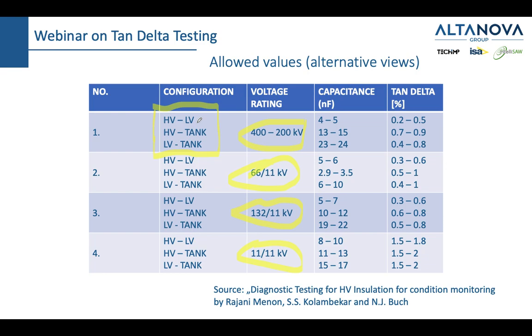what we can see is that for extra high voltage, the insulation between high and low voltage side should be very good, between 0.2 and 0.5, which is much less than 1%. High voltage versus tank is between 0.7 and 0.9. If it's smaller, even better. And low voltage tank is between 0.4 and 0.8. And also we have some capacitances here. Now, a capacitance is really difficult to assess. It's not difficult to assess, it's difficult to say what would be the nominal values because it depends heavily on the construction, on the design of the transformer, on some of the materials which are being used. But these are some, I would say, guidelines when we talk about capacitance.